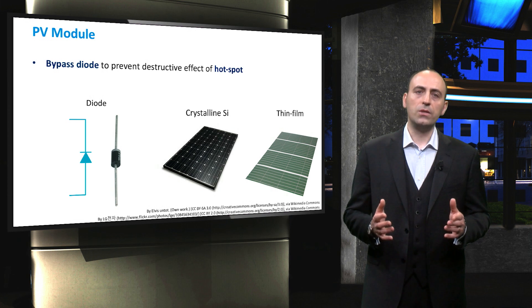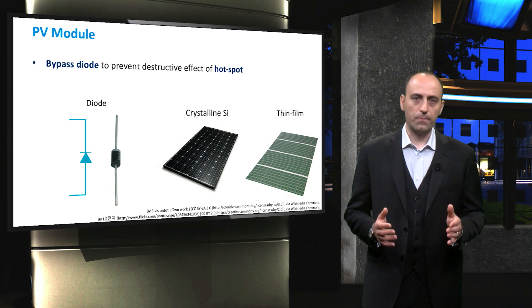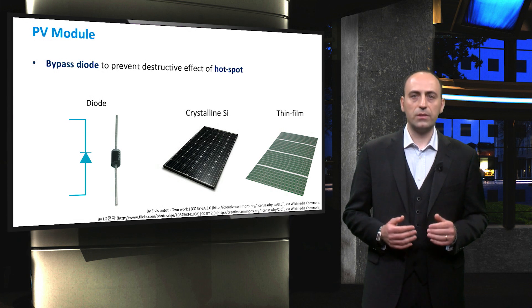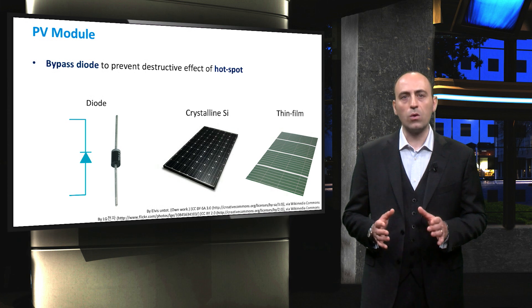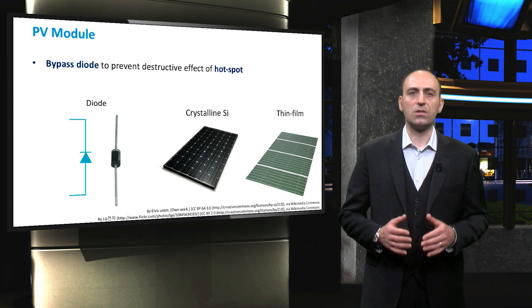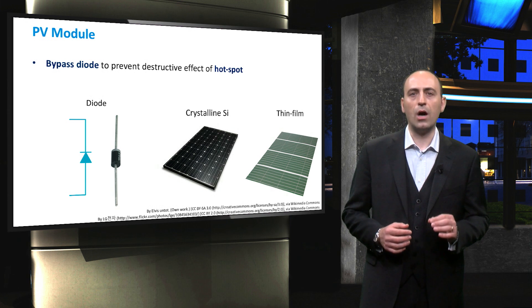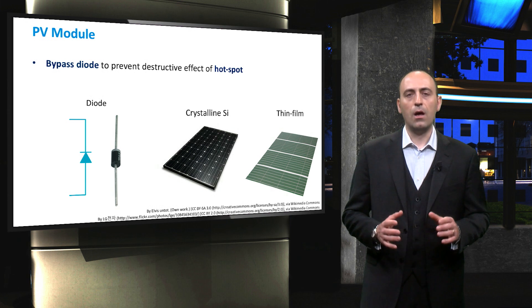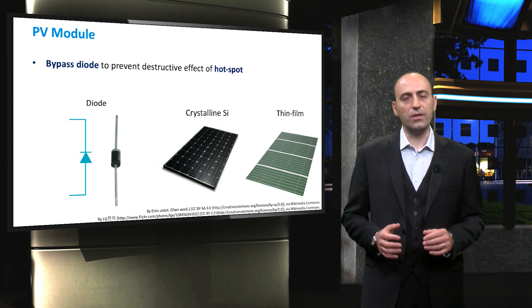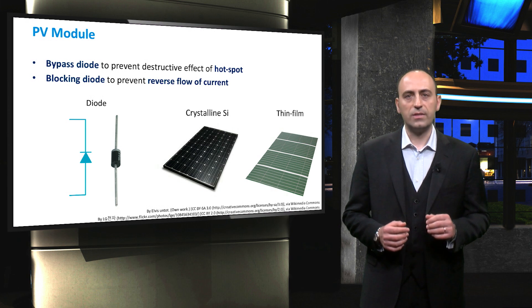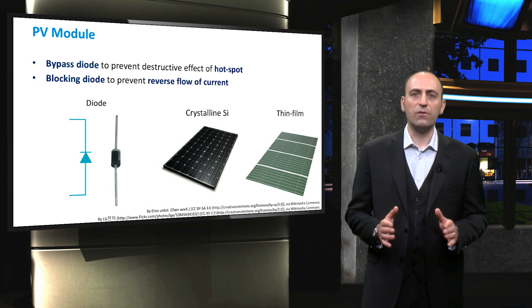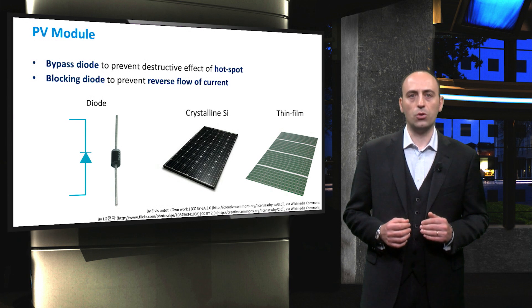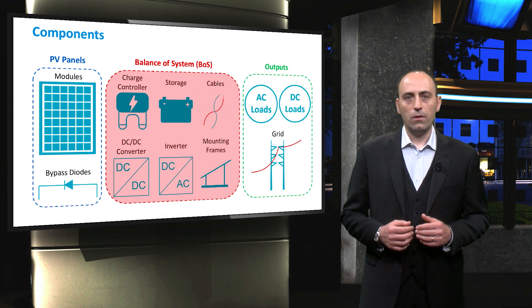In many modules, there are other important components. The first is the bypass diode, usually placed in the junction box of the module. It protects solar cells to avoid a so-called hotspot. Hotspots will be discussed later in the course. The second is the blocking diode, which prevents current from flowing from the external circuit into the PV module.